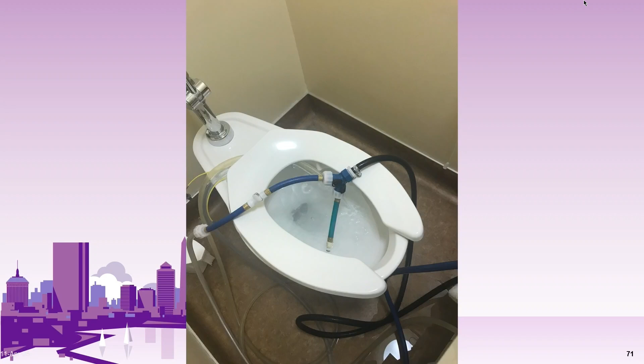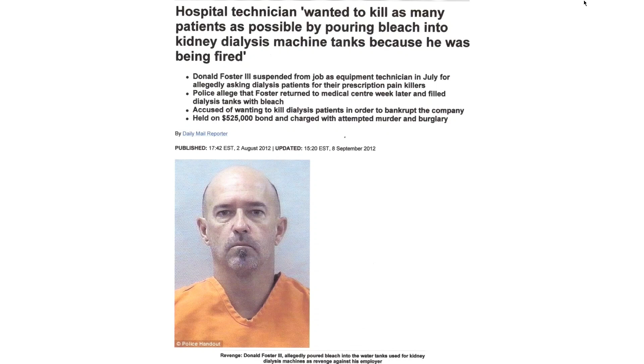This is the reason why we lock our water room. A hospital technician wanted to kill as many patients as possible by pouring bleach into the kidney dialysis machine tank because he was being fired. And the only reason they discovered this was the policy of that unit. Their policy was that at the beginning of each day, you test your water. And that was the only reason it didn't get to the patients. That amount of chlorine that could harm our patients is so low that it will not change the conductivity in your machine. So the patients would have been subjected to direct inoculation of that agent through the dialyzer. So lock your water room.